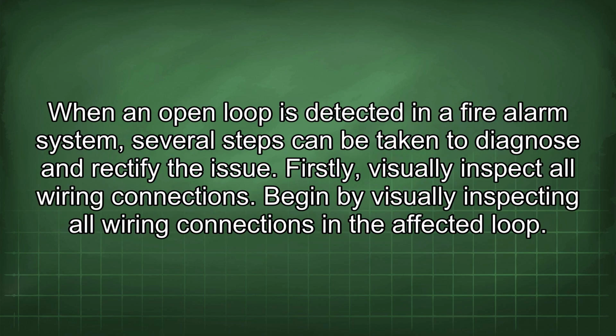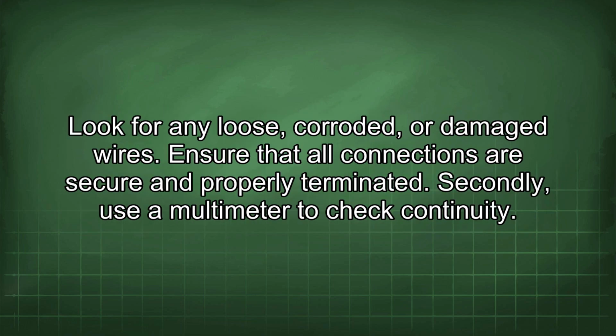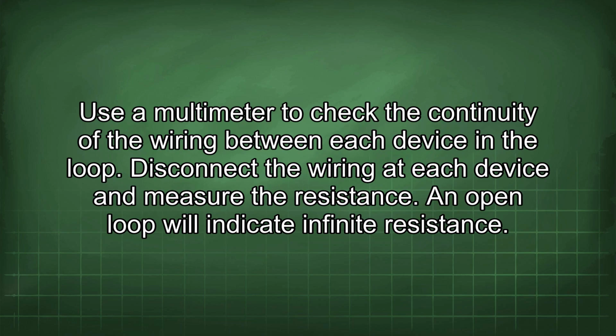When an open loop is detected in a fire alarm system, several steps can be taken to diagnose and rectify the issue. Firstly, visually inspect all wiring connections. Begin by visually inspecting all wiring connections in the affected loop. Look for any loose, corroded, or damaged wires. Ensure that all connections are secure and properly terminated. Secondly, use a multimeter to check continuity. Use a multimeter to check the continuity of the wiring between each device in the loop. Disconnect the wiring at each device and measure the resistance.